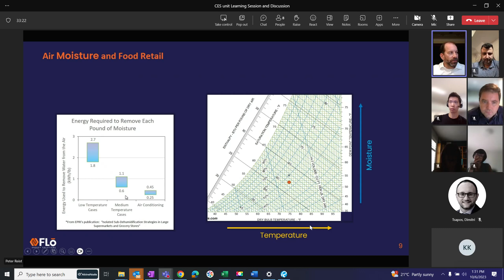The medium temperature cases, you could use them as well, and that happens in bad designs. Or you can let the air conditioning do it. And the air conditioning is the most efficient way to remove moisture. And of course, the reason is that we don't let the moisture freeze on our coil. We don't have to run to those low temperatures. We maintain our coil at the optimal point to pull moisture out without freezing and having to defrost our coil and all these things. So that's why we're the most efficient at it. And that is our purpose.